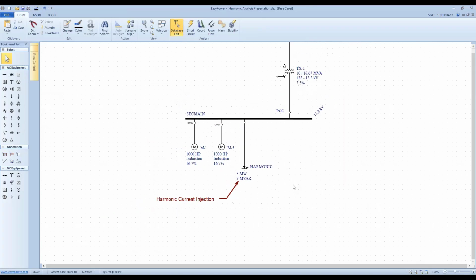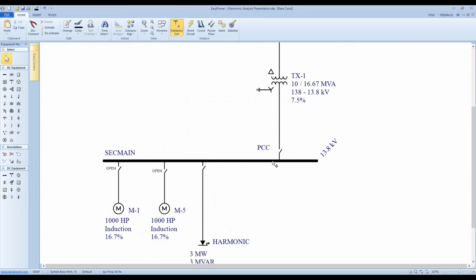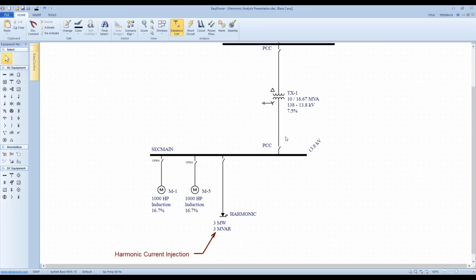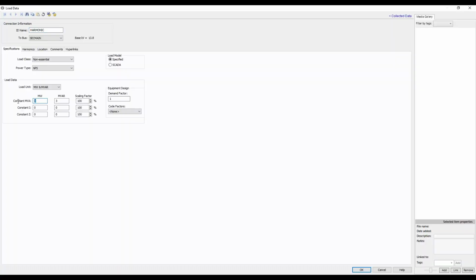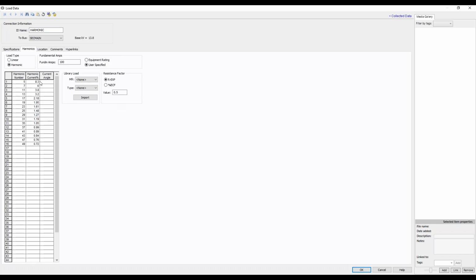Sometimes somebody might have gone out and taken measurements at the point of common coupling at the main incoming of a small system like this. Those measurements I would then put into a load down here, and oftentimes it may be a 0 megawatt load like this, a 0 megavar load like that, and then I have just harmonic current input. So it does not impact the load flow analysis. It only impacts the harmonic analysis package. So there's a couple different ways of doing it.